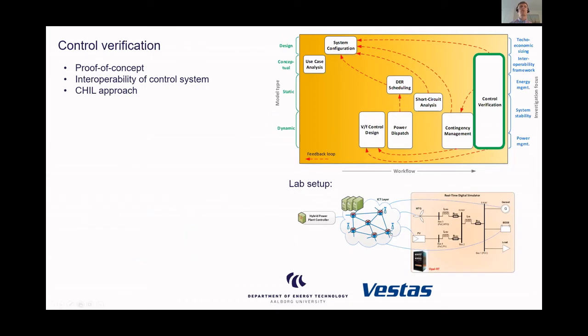Finally, as a last stage, as a proof of concept, you need to address the interoperability of the control system, which I have done with the so-called control hardware in the loop approach. So by using the lab that I previously explained, having all the units modeled in a real-time simulator, and having the central controller placed in a real PLC platform, then you can verify both technical and economic performance criteria. Technical also relates to how to cope with communication losses and failures, which might require some modification of the control design in the first place.